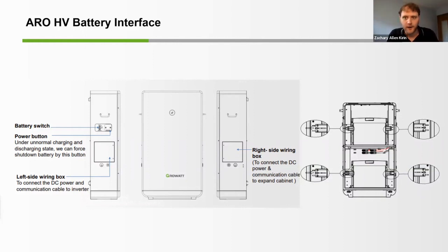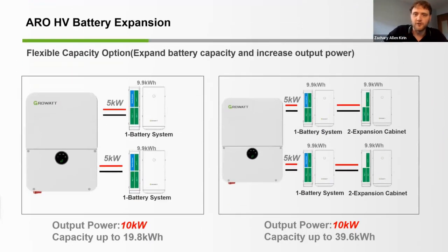The picture on the right kind of shows how the battery modules are implemented into the battery pack. So up to 3 battery modules may fit inside of the ARO high voltage battery cabinet. So there'll be one main module on the top and then 2 secondary modules on the bottom. Up to 3 of those modules makes 9.9 kilowatt hours, at 3.3 kilowatt hours capacity for one single module. It's very easy to install as well.